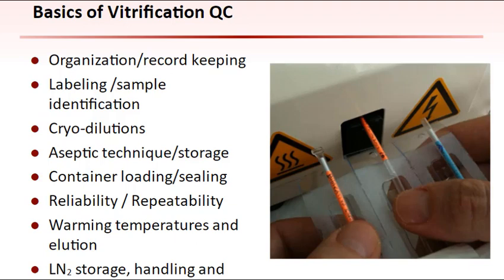Reliability and repeatability: is the vitrification system simple and easily repeatable in its daily application among all technicians? Can embryos and oocytes be consistently recovered without a risk of loss? Warming temperatures: is the warming potential of the device compatible with the vitrification solution used to ensure optimum survival and developmental competence? Liquid nitrogen storage, handling, and shipment: because of the potential adverse effects of uncontrolled, suboptimal warming of vitrification microdevices, the ability to maintain specimens below minus 150 degrees Celsius during storage, identification, verification, and possible shipping and receiving is of paramount importance.